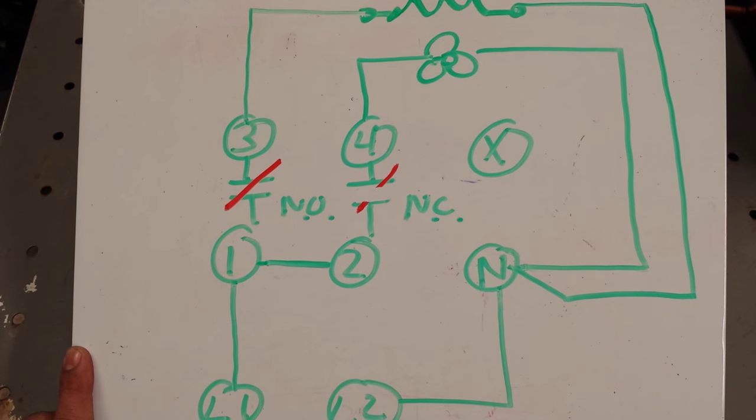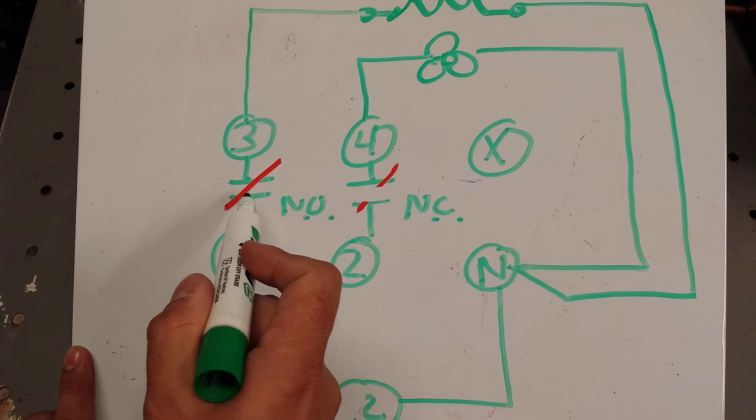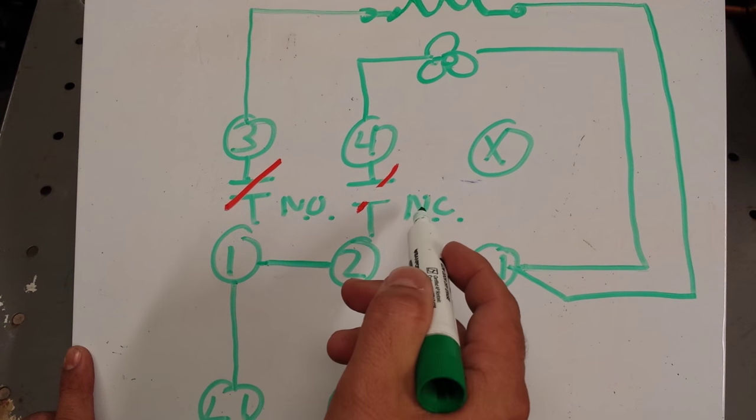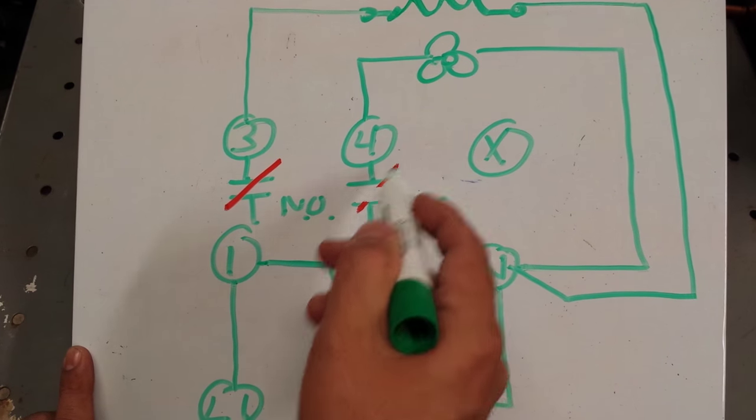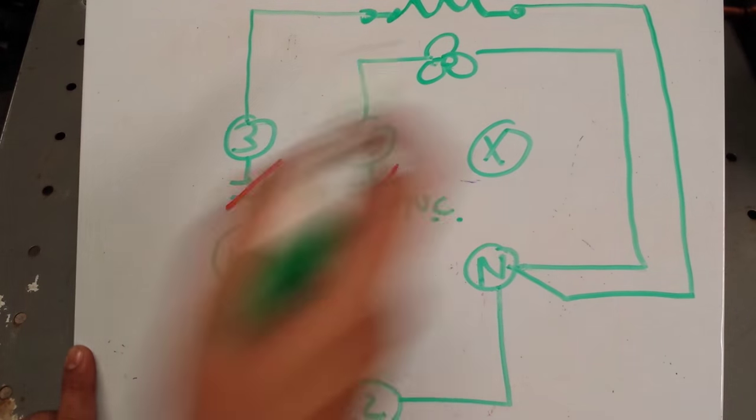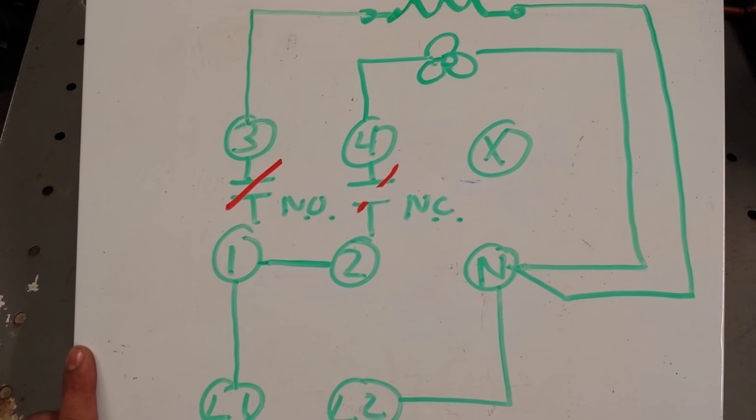When defrost ends, the contacts will revert back to their original positions. This one will reopen back up. And this terminal, this terminal contacts will close. Heaters will turn off and the fans will turn on.